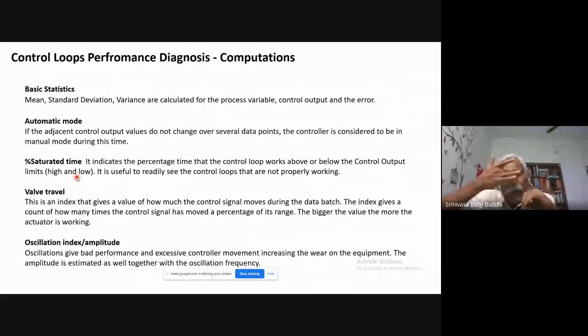Okay. Then we have the valve travel. This index calculates how much the control signal moves during this data batch. This actually gives information about the vigorousness in the control action, because it is not a desirable state. If there is too much travel, it leads to a lot of wear and tear on the control valve actuator.